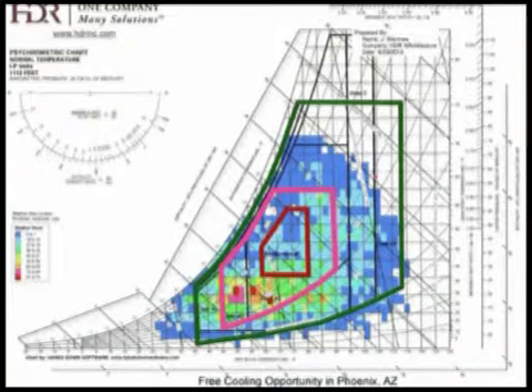And this is going to be focusing probably on air side and water side economizers. In some locations where you really don't want to go to the absolute minimum relative humidities within the space, you may want to look at a combination of both an air side as well as a water side economizer. And when you've got climates with extended hours of very dry conditions, such as the high desert in areas such as Phoenix, you definitely want to be looking at the evaporative cooling opportunities.